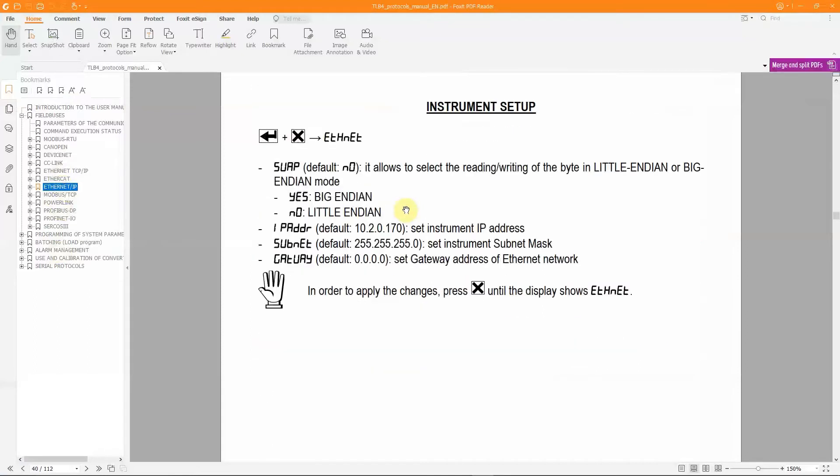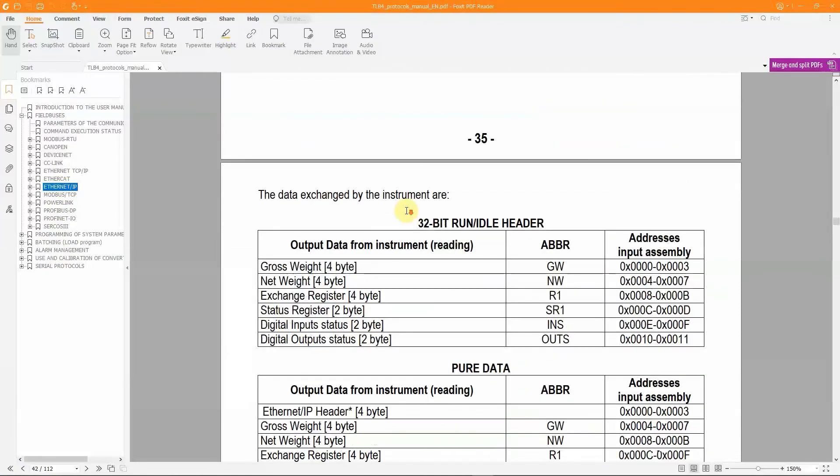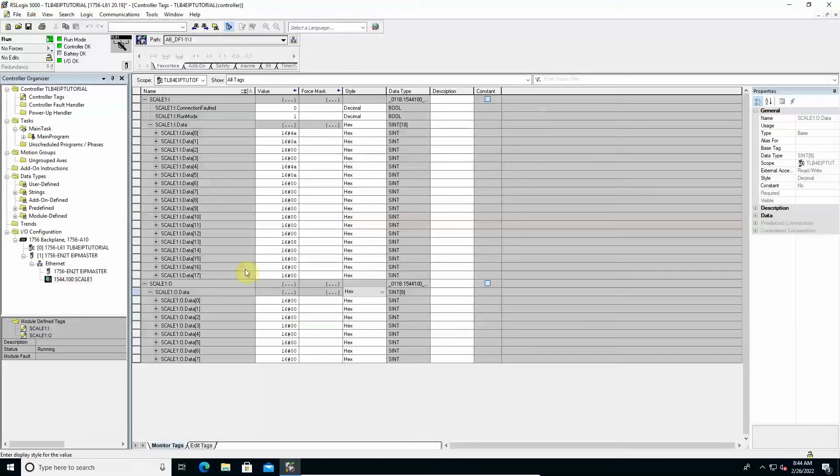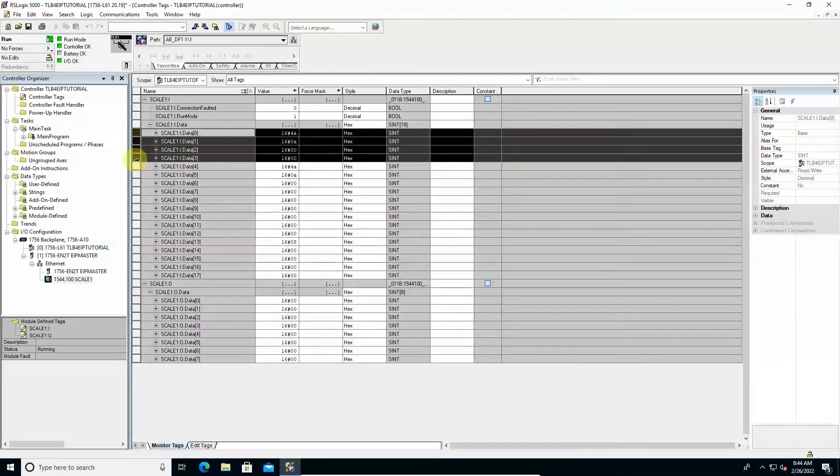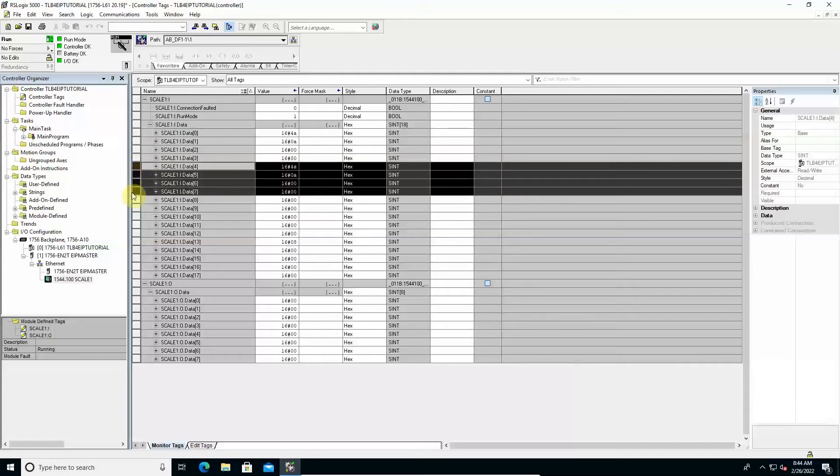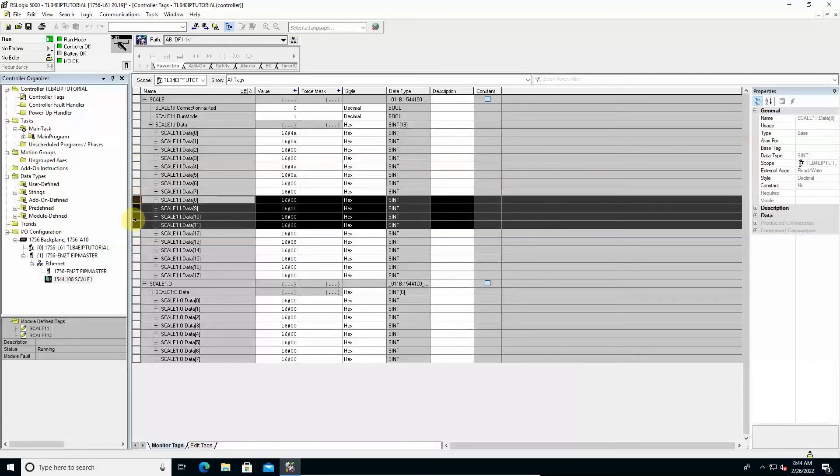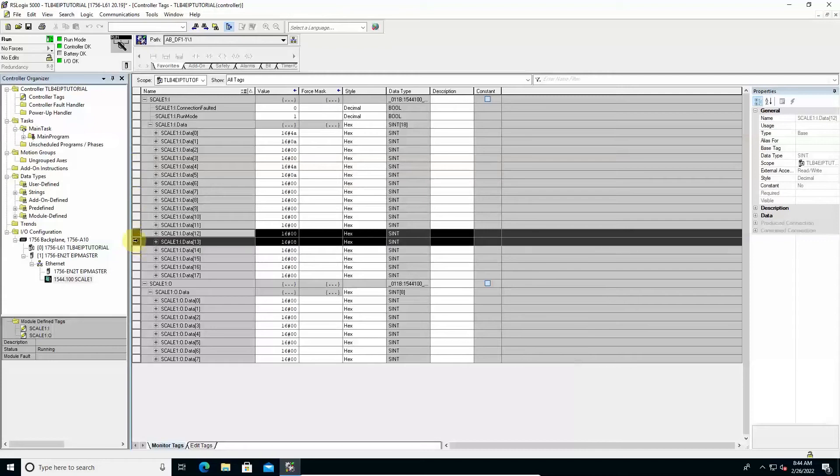In the section dedicated to the Ethernet IP interface, with the use of an EDS file as in this tutorial, the table to refer to is the one relating to 32-bit Run/Idle header. Among the input data received by the PLC, we have the 4 bytes that make up the current gross weight value, the 4 bytes for current net weight value, the 4 bytes for the output exchange register, the 2 bytes for the status register value, and so on for the other parameters described in the table.